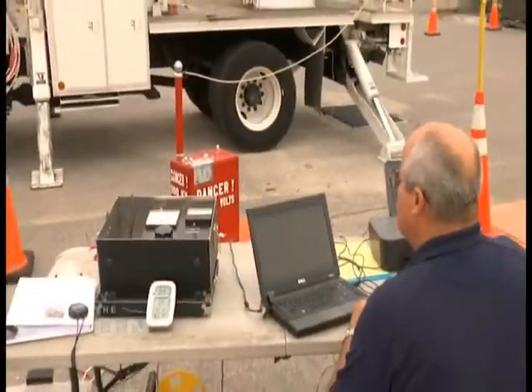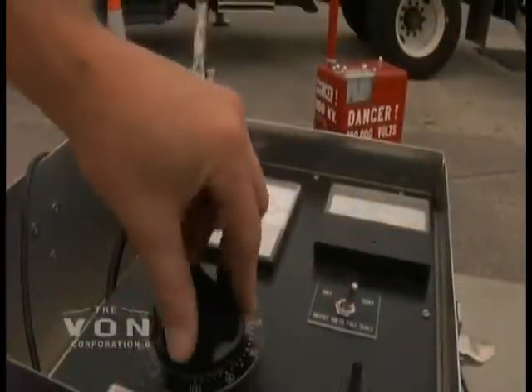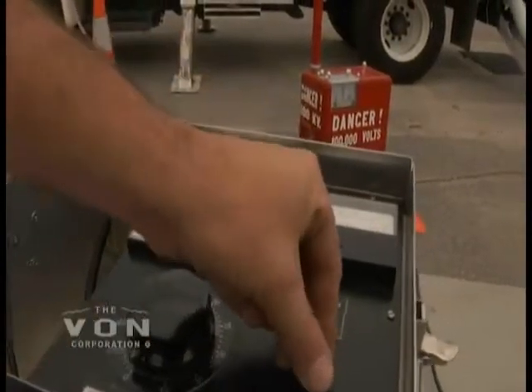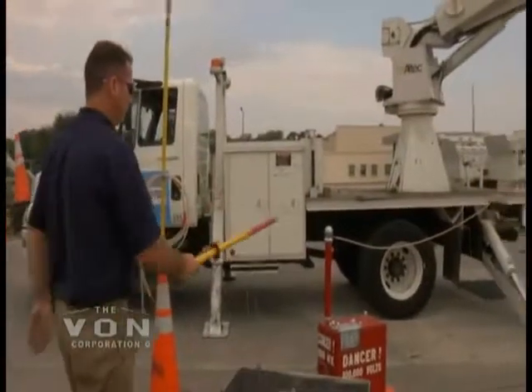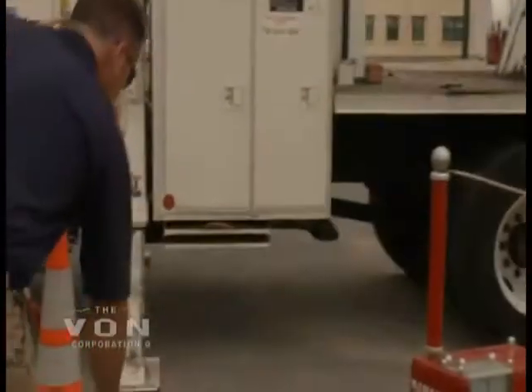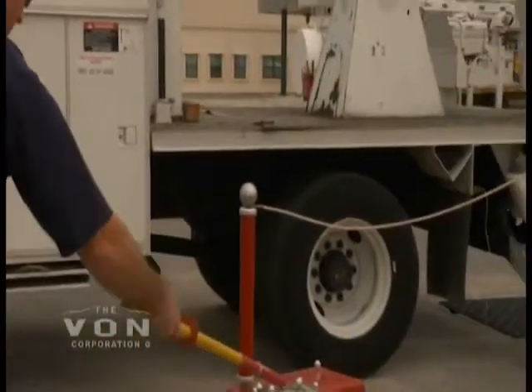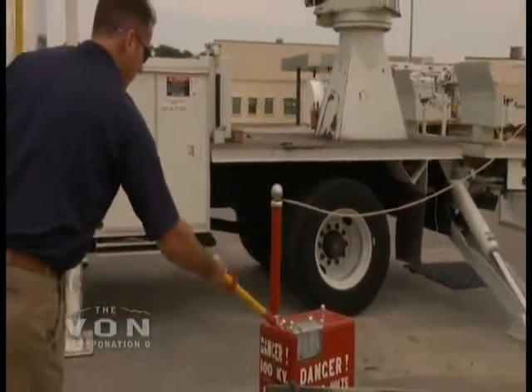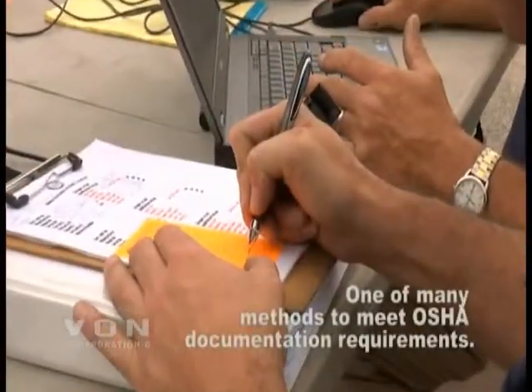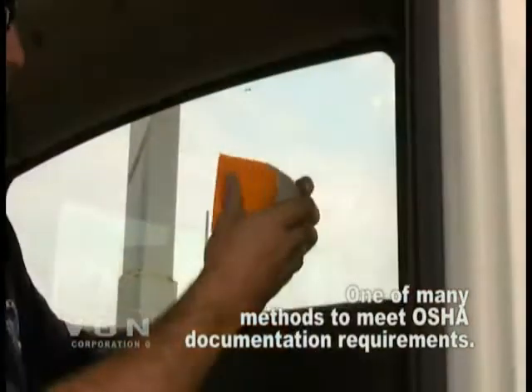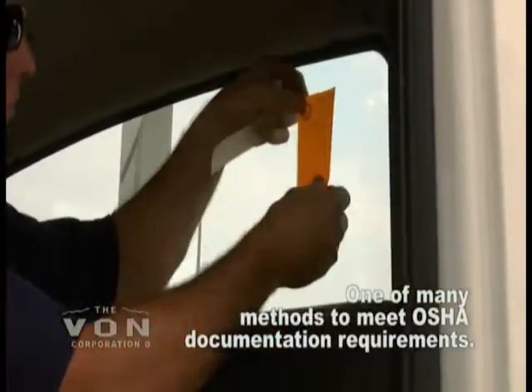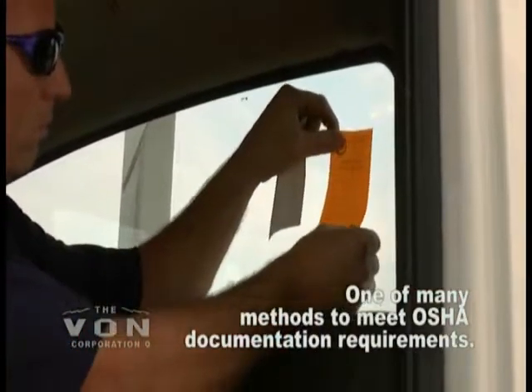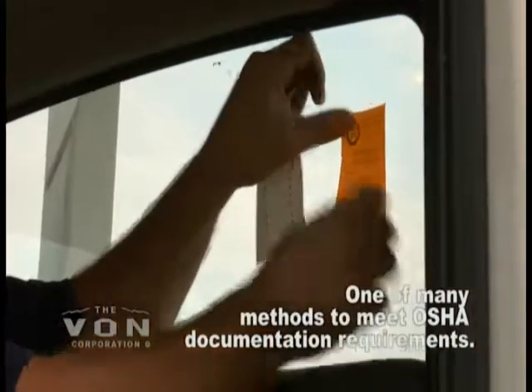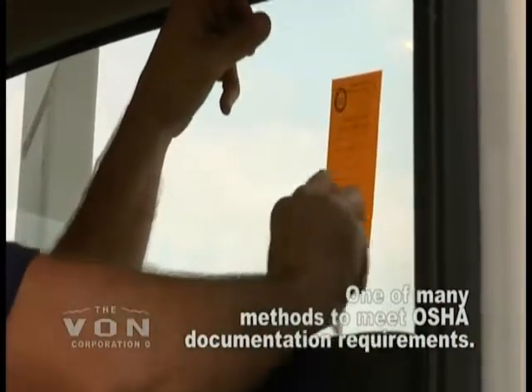Test is now run. We're grounding the unit. We've used our ground resistor stick to bleed the unit off, and then we're placing our hard ground on, and the unit is now grounded to where we can operate the truck. We provide a sticker in the back glass of the truck. This gives you the date that it was tested, gives you the truck number, serial number, the voltage that was applied at each test, and the microamp reading of each test.